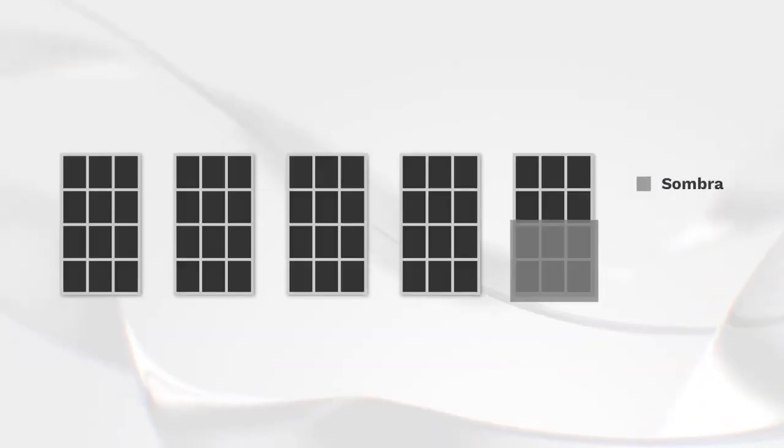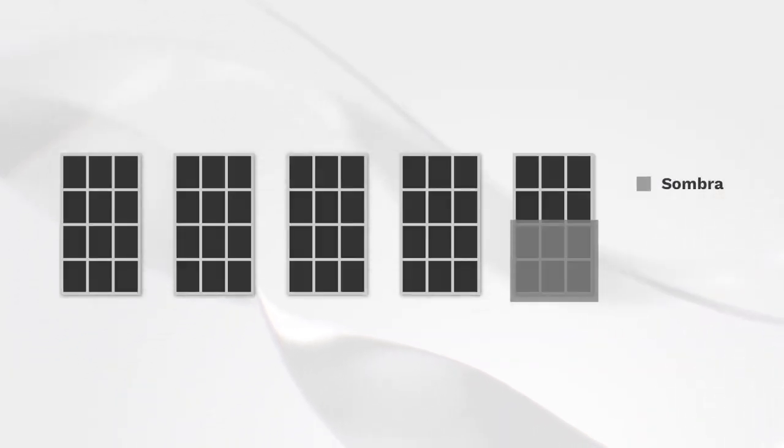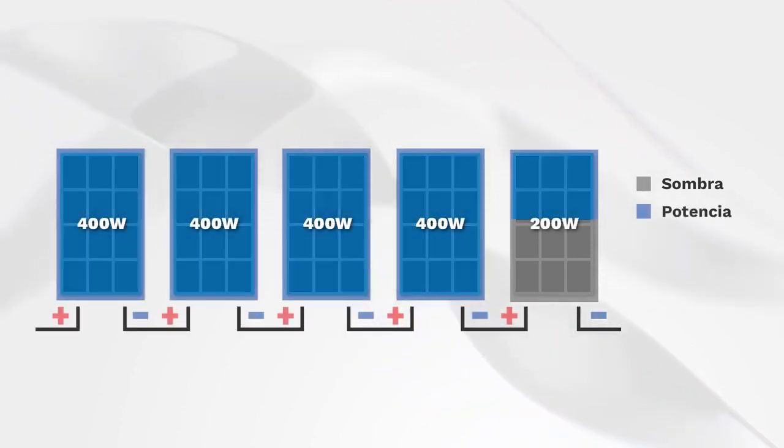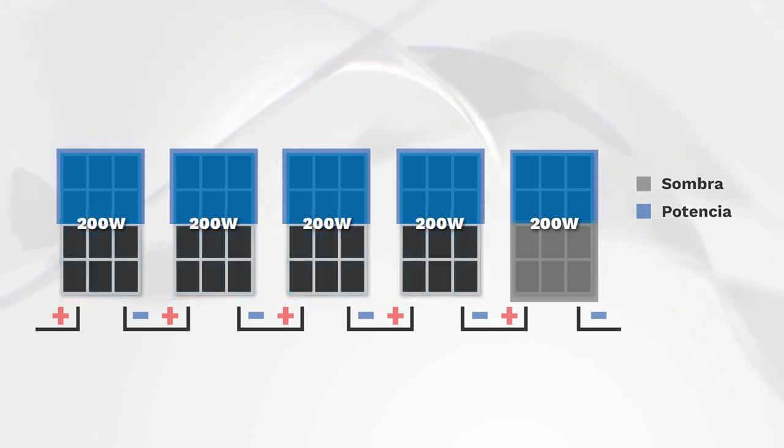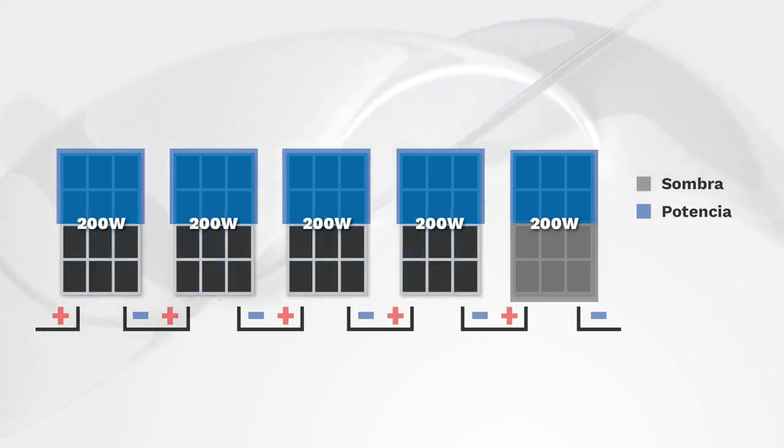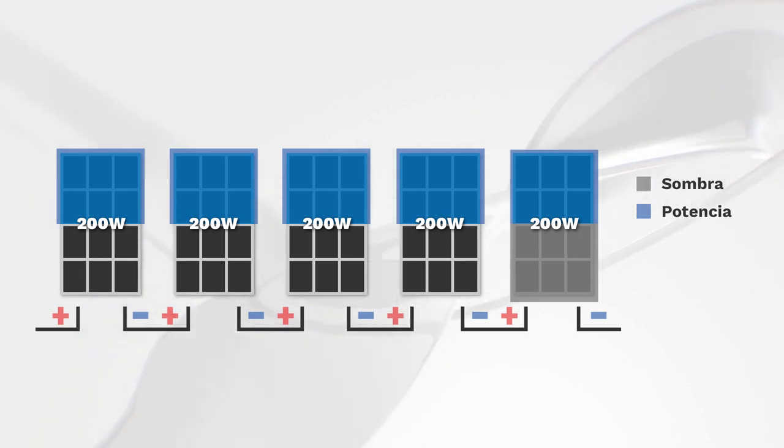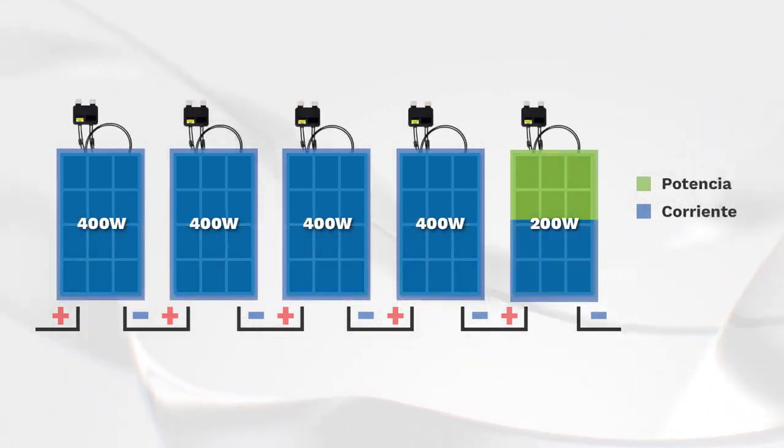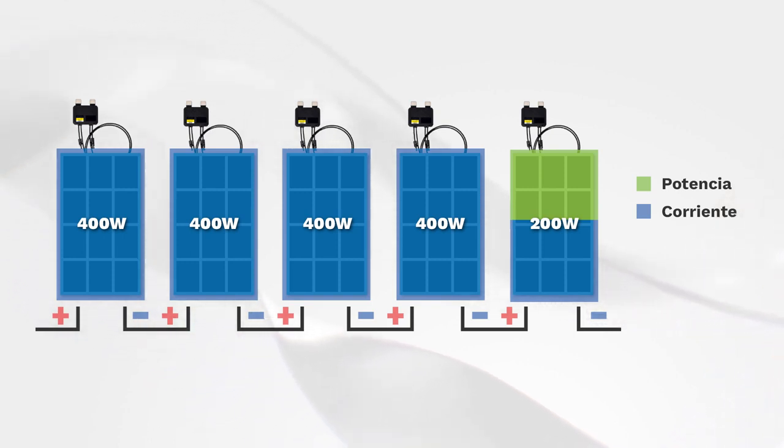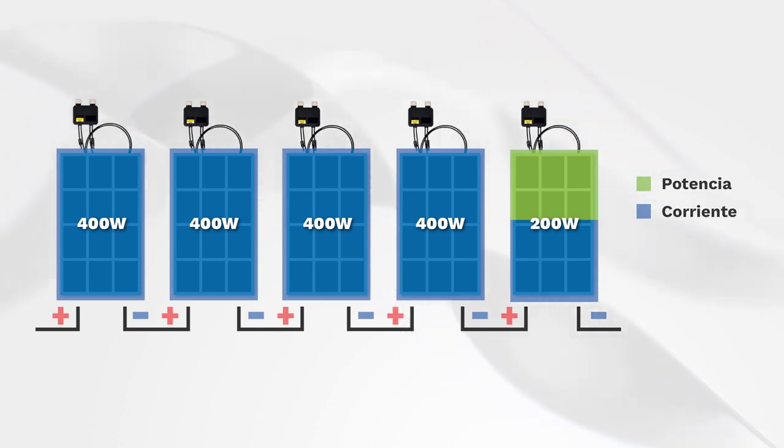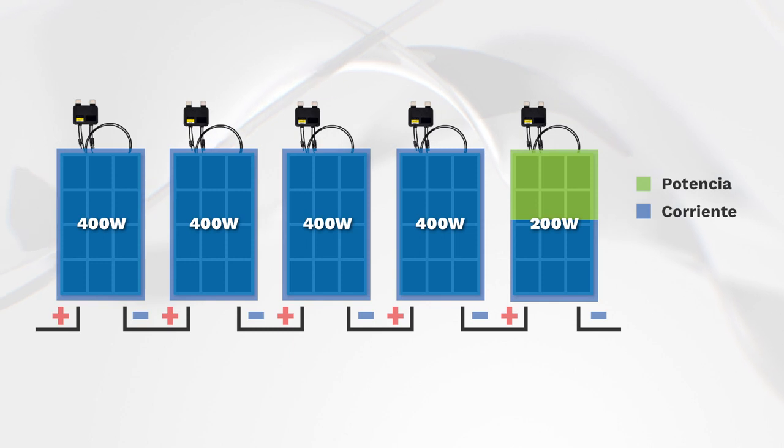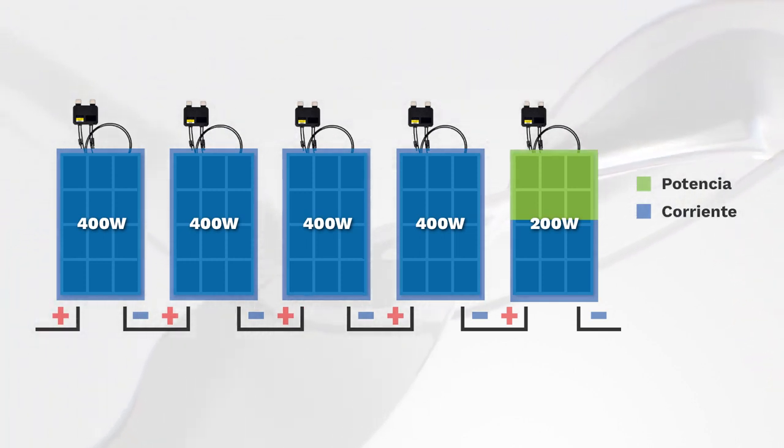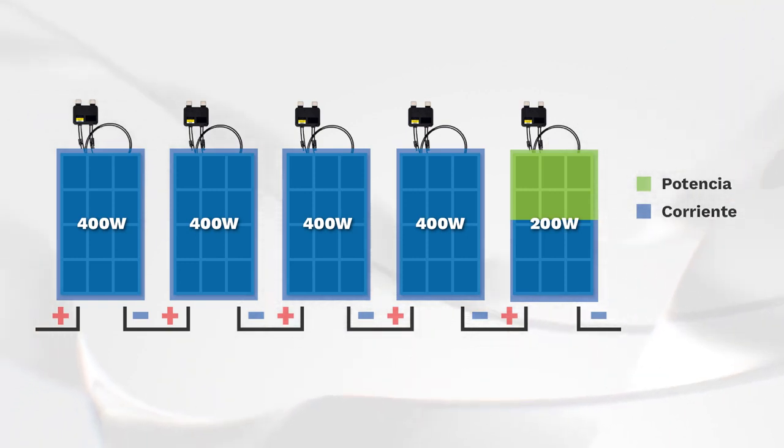If we had any panel that for some reason was shaded, this solar panel is going to stop generating the same energy as the others. And since all of them are placed in series, when one of them has a lower current due to the shading, all the others will also lower their current. And that means that the total production of your photovoltaic installation will decrease. If what we do is place an optimizer on each panel, what will happen is that by lowering one of its current, this panel instead of lowering the current, will change that difference in power by voltage and will maintain the same current of the entire chain. The loss of power will be only the power of the module and will not affect our entire string of panels.